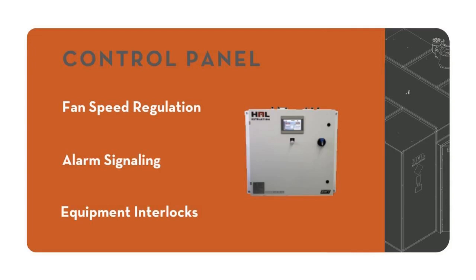So a couple examples of our interlocks would be the fan and light interlock. The fan and light interlock is that you can't have lights on without the fan. And so that's a code that requires that. There's a code that says you can't be in this room operating without the fans being on. So that's the interlocks. After the fan and lights, then you have a heater ancillary component interlock.